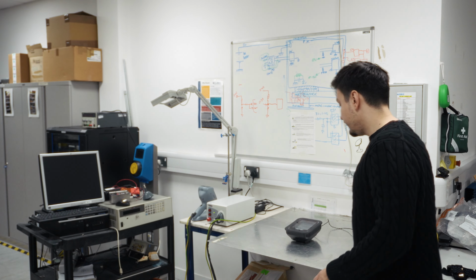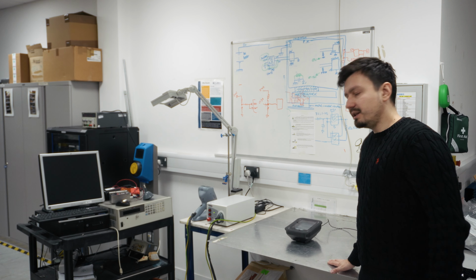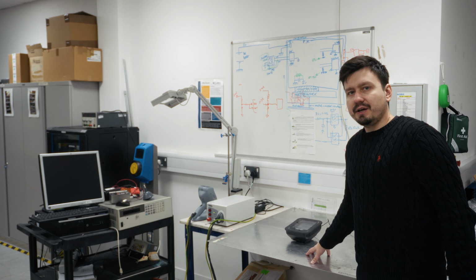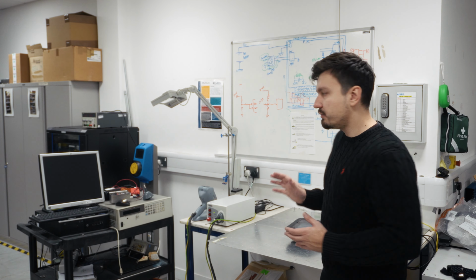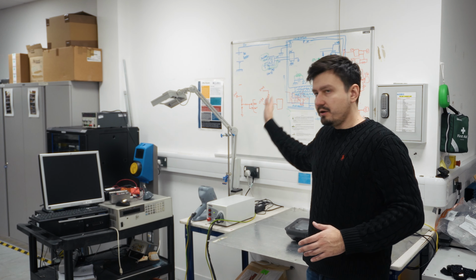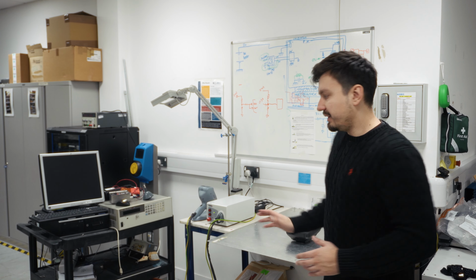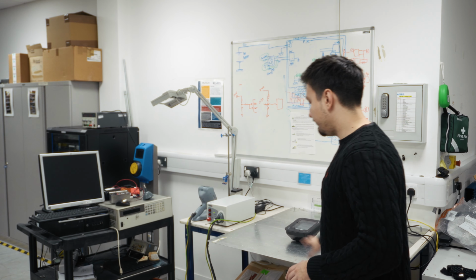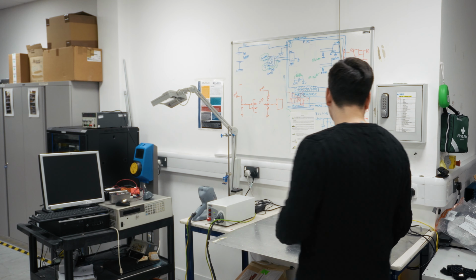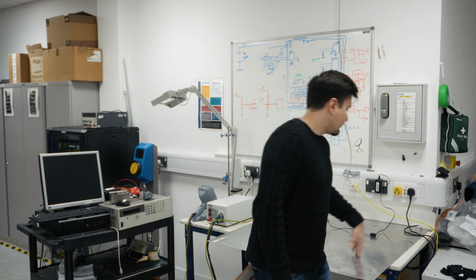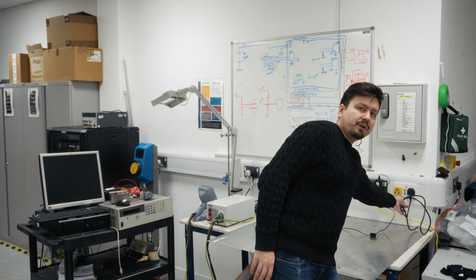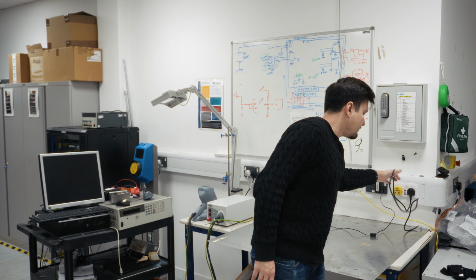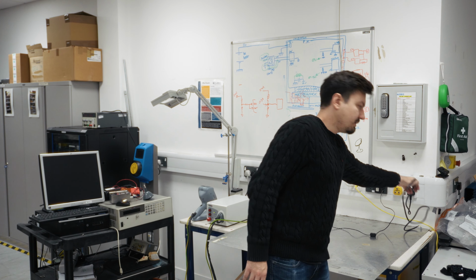So now we are ready to begin the test or start preparing for it. The first thing that I have here is the metal plate below the device under test. Now, if I were doing this test according to the test standard, I would also have a vertical coupling plane, but I do not have that, so I only have a horizontal coupling plane. And very important, I have grounded this plane into the building by connecting this lead into the socket.